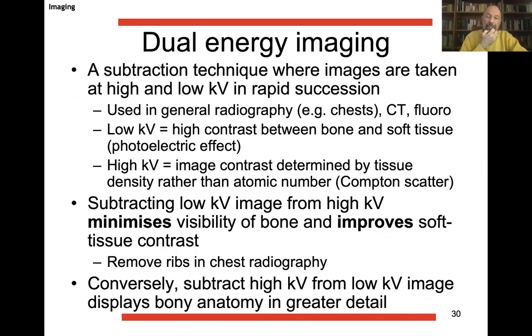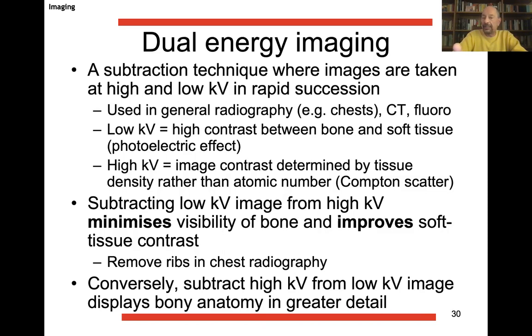Another important innovation in x-ray imaging is dual energy imaging — a subtraction technique where images are taken at high and low kilovolt in rapid succession. Subtracting the low kilovolt image from the high kilovolt image minimizes visibility of bone and improves soft tissue contrast, effectively removing the ribs in chest radiography. Conversely, subtracting high kilovolt from low kilovolt gives bony anatomy in much greater detail, because low kilovolt gives high contrast between bone and tissue via the photoelectric effect, while high kilovolt image is determined by tissue density via the Compton effect.